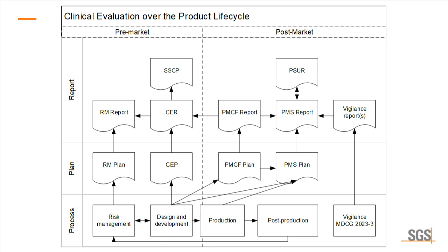When it comes to the post-market evaluation and clinical evaluation over the whole product lifecycle, you can see that basically it starts at the risk management and design and development processes early on in the device lifecycle, and then you will iterate on these as you go forward. So from the risk management, you will create a risk management plan. Then when you carry out a given round of activities, then you will generate a risk management report, overall risk management file. From the design and development, you will have the clinical evaluation plan. When executed, it will result in a clinical evaluation report.